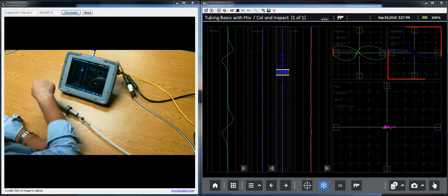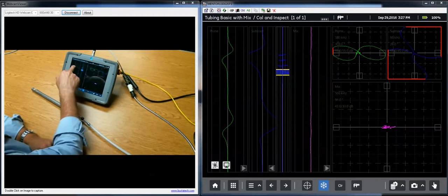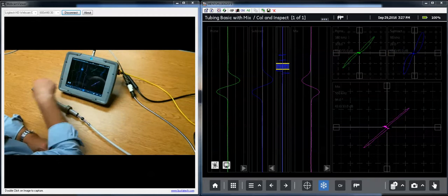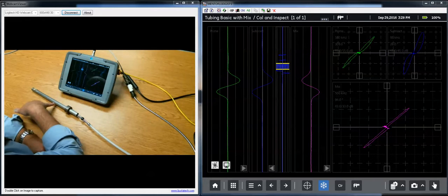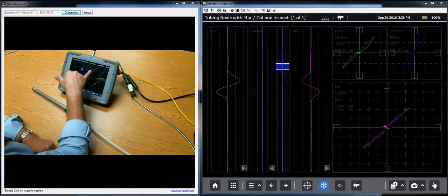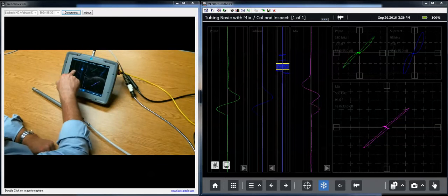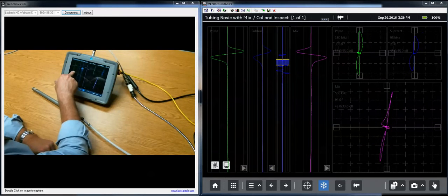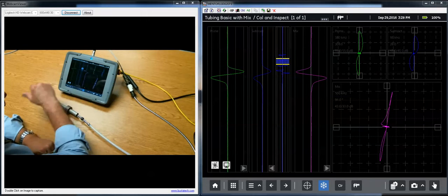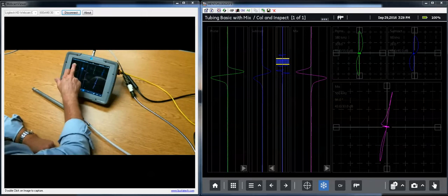Now you say, what happened to our flaws? All right, let's walk back in time. There is the flaw that goes 1/4 of the way through. So we get a signal that looks very much like the prime. There's the halfway signal. All right, so we're a little bit phase shifted. We have a little bit of change, but still a very recognizable flaw.